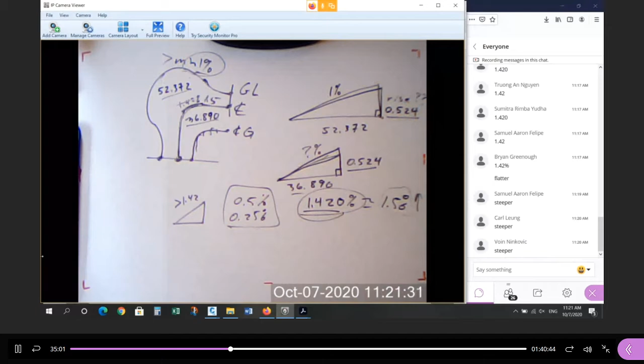Okay, how you input all this into the system is going to be a different calculation. So once you draw, and here's another example of why you have to correct any mistakes that might happen on the previous assignment. If we go back to AutoCAD, if you draw this correctly, you can get the length, the run, the distance, from the drawing, right? But if these are drawn incorrectly, then this entire calculation is going to have to be revisited. Okay, so that's how you design the profile on center so that you guarantee a minimum gutter grade on the outside of the elbow at 1%.